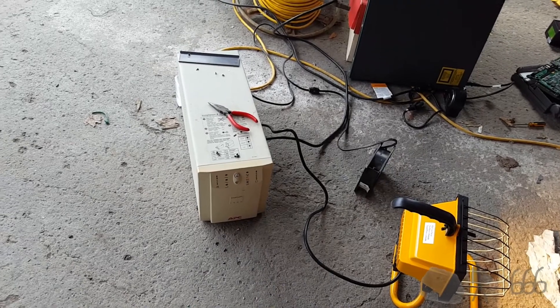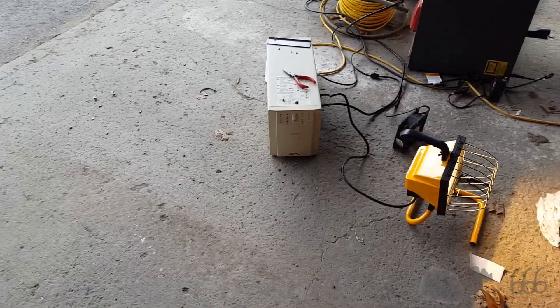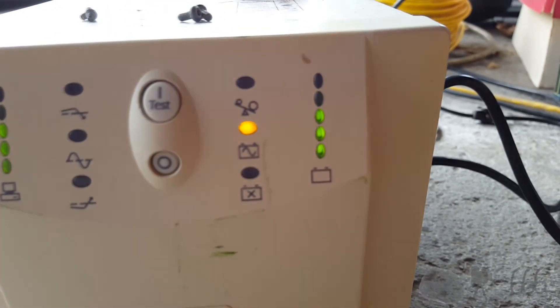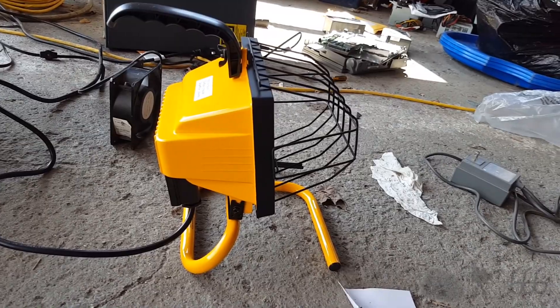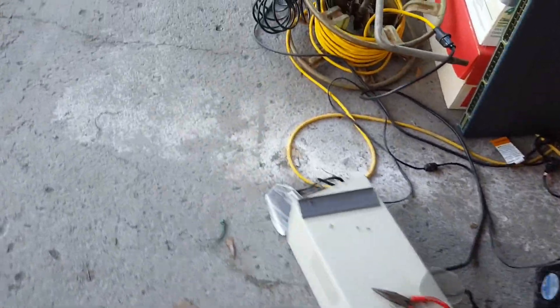Now you just have to let that thing drain. When doing this, you've got to let it run all the way down. The battery gauge is not going to be accurate during this process, so I wouldn't trust it. The UPS has now dropped the load.